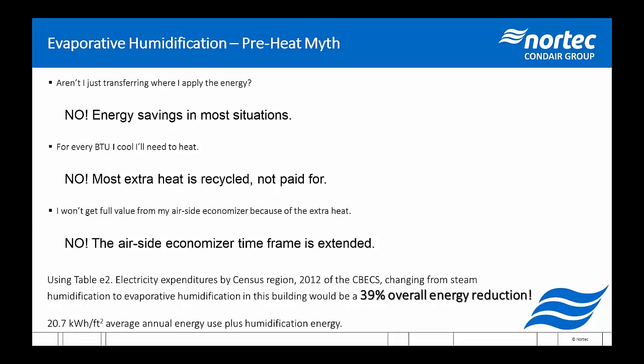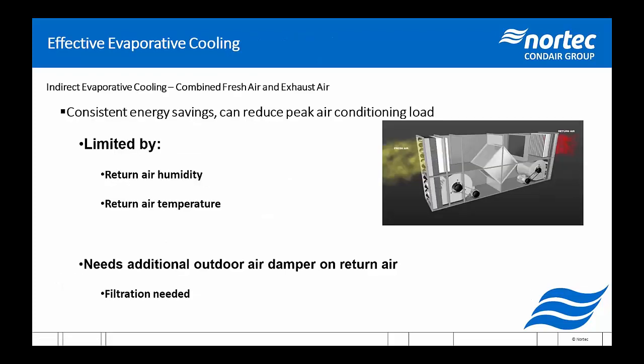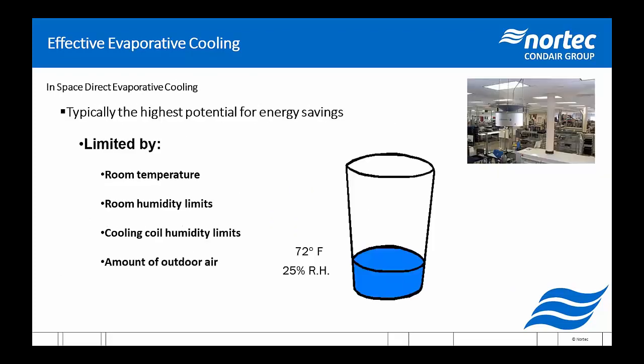So I've got a question. What would be my product of choice for energy savings? As I said at one point in here, but it's a good question. I should make it a little clearer, I think. Let me see if I can find the slide. Typically, your in-space evaporative cooling is going to be your greatest potential for energy savings, which means to do in-space cooling, you are going to be using a high-pressure system, our ML system, for example, or you'll be using compressed air fog, or jet spray system. And again, the reason I prefer this is the amount of cooling we're able to do and be effective without over-humidifying is significantly more than in the other in-duct systems.